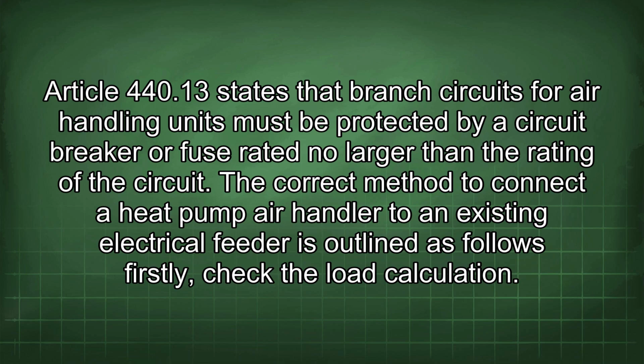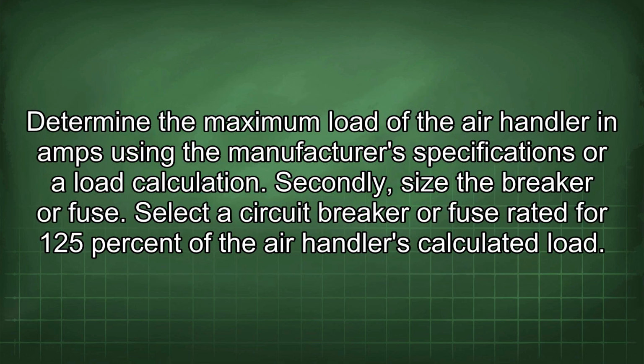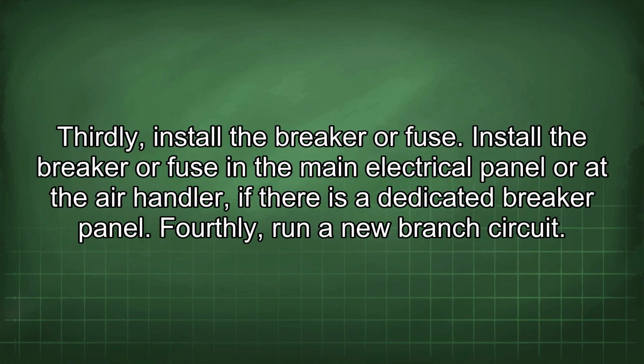The correct method to connect a heat pump air handler to an existing electrical feeder is outlined as follows. Firstly, check the load calculation. Determine the maximum load of the air handler in amps using the manufacturer's specifications or a load calculation. Secondly, size the breaker or fuse. Select a circuit breaker or fuse rated for 125% of the air handler's calculated load. Thirdly, install the breaker or fuse.